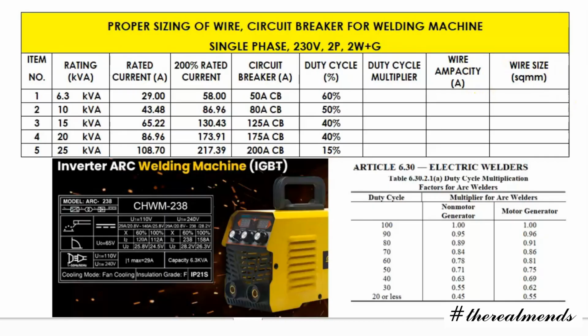The next is the duty cycle column in terms of percent. If you notice, we have 60% duty cycle. Sir, where did you get that? Actually, we get that from the nameplate. Here, the 240 volts, the X is 60%. It's optional, there is 60 and 100%, and it is mostly not used, so we can assume 60%. For the next, 10, 15, 20, 25 kVA, we just assume 50% for 10 kVA, then 40% for 15, 40% for the 20 kVA, and 15% for the 25.